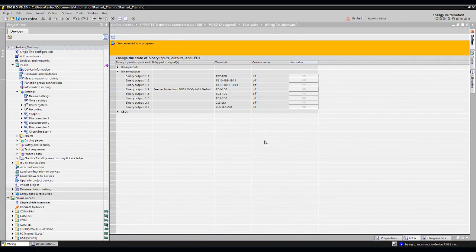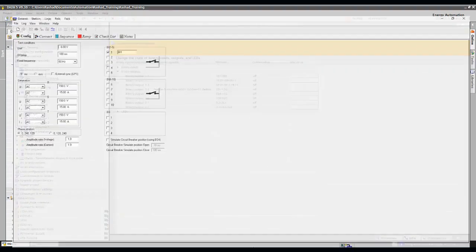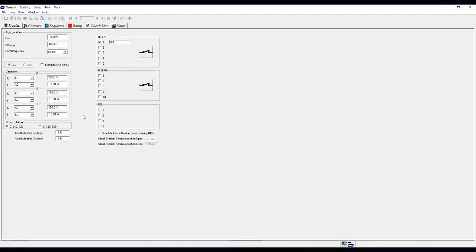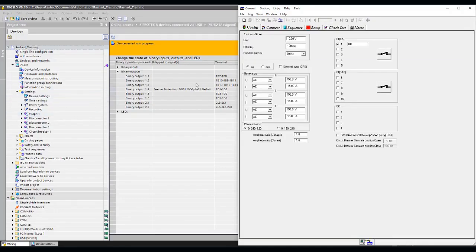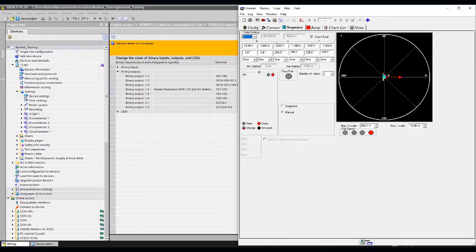What's left for me is the measurement. So in measurement, quite simply, we will use test devices like the Freja. We will set the frequency to 60 Hertz. We will go to the general page instead of sequence, and we will choose manual, very normally. We will verify the full voltage and set the phase voltage to 69.28. 120 divided by root 3, which is 69.28.